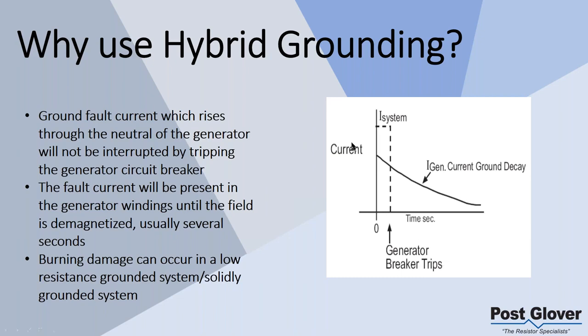So there was a significant amount of damage. That is what can happen when you have internal faults in your generator. If this was a solid ground system, you probably need a new generator. If you have a low resistance ground system, you're going to have some serious rework probably, just because of this extra time that it's winding down. So you basically need to account for this, and that's why you're not fully protected. Even though in the vast majority of situations you're protected with the low resistance ground system, you're not fully protected on the medium voltage generator unless you have a hybrid grounding system.